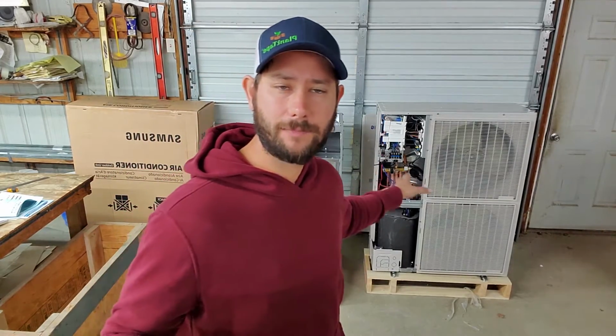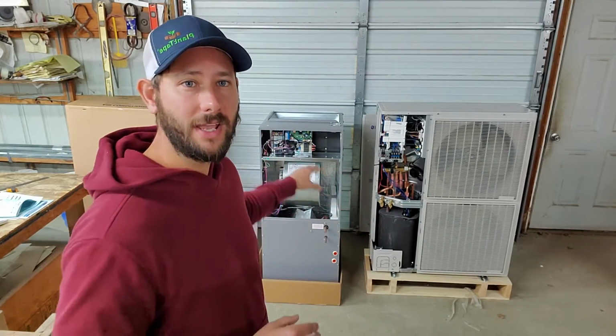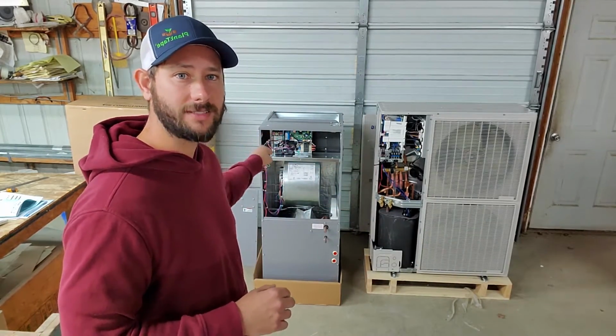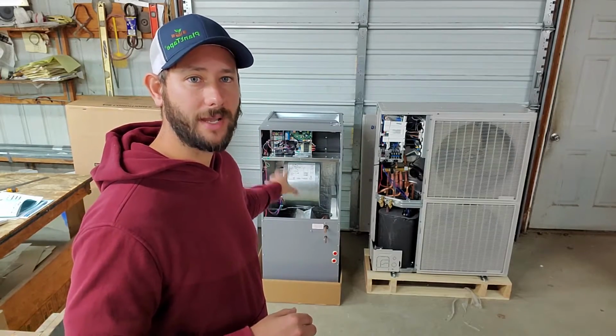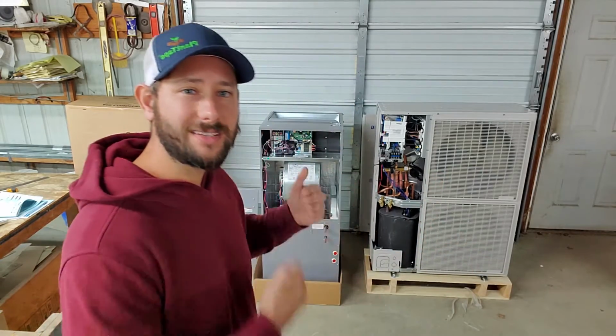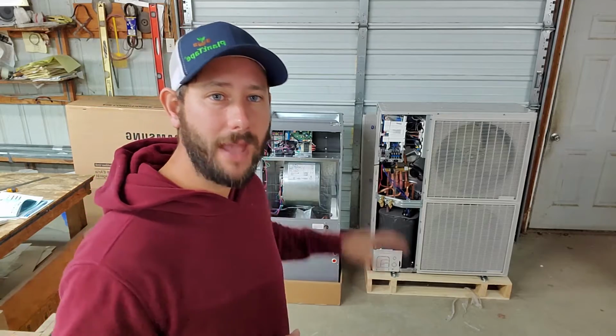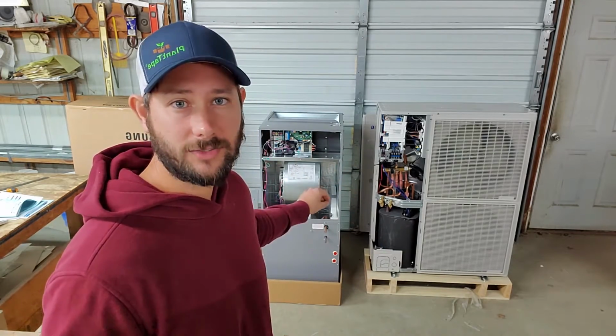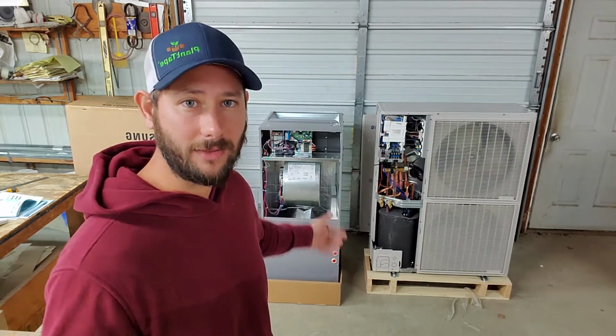Now let's talk about defrost. Defrost lasts around 12 minutes, depending on the accumulation of ice and outdoor ambient conditions. And during those 12 minutes, your evaporator fan motor, this constant torque, high efficiency fan motor right here, is going to idle. It's not going to blow through the duct and just cause a cold draft. What it's going to do is it's going to idle. And it's measuring the temperature, because you've got sensors on your evaporator, your inlet and outlet sensors are going to measure temperature, and they're going to reach a target of around 99 degrees.